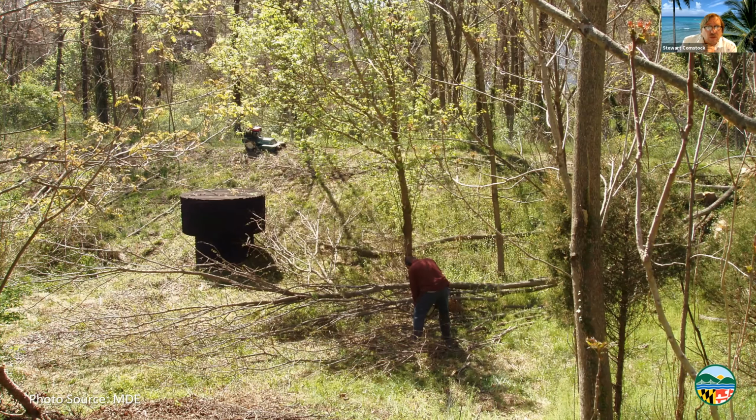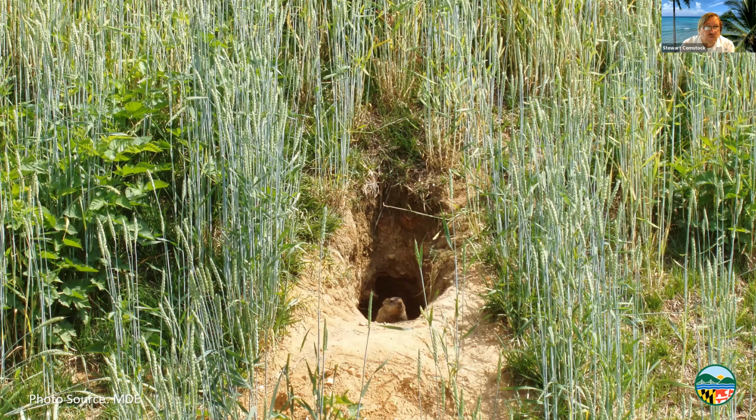And while this young guy might seem to be innocent, hiding in his little hole in the side of this dam embankment, it is not merely sufficient to fill in these holes, for we do not know how deep they go and how much damage they have caused to the dam embankment. This again is an example of maintenance that would require approval.